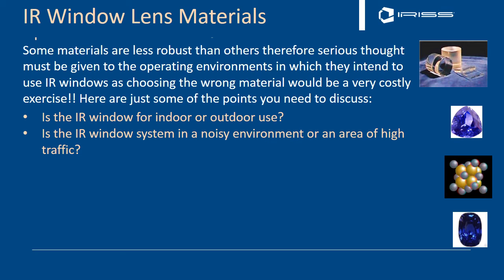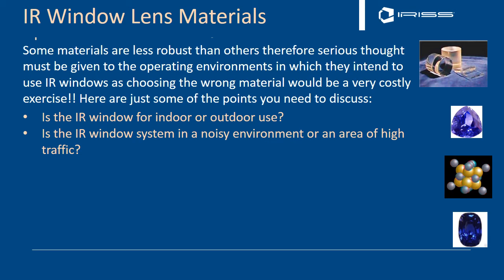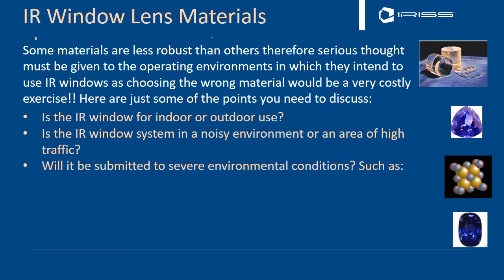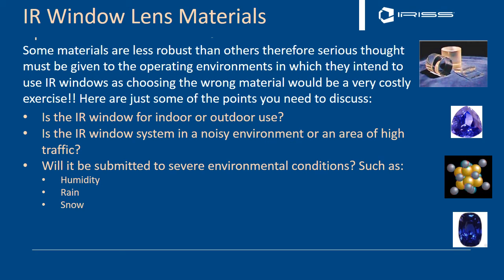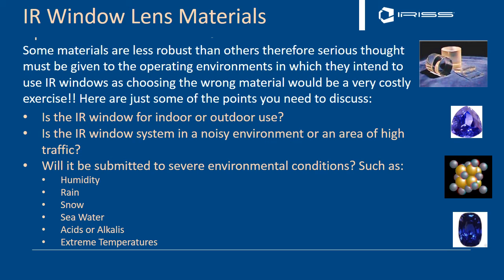Industrial environments are very noisy. High frequency noise and vibration can affect the transmission rate of crystals because they are very fragile. I've seen crystal windows being broken from someone just hitting the side of a cabinet — which happens regularly in industrial applications — and even find them broken on delivery. You also need to consider whether the window will be subjected to severe environmental conditions such as rain, humidity, snow, seawater, acids, alkalis, or extreme temperatures. There are a whole bunch of factors to think about before investing heavily in your infrared window.